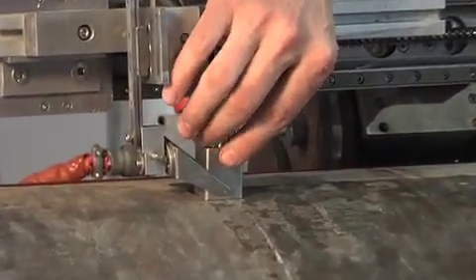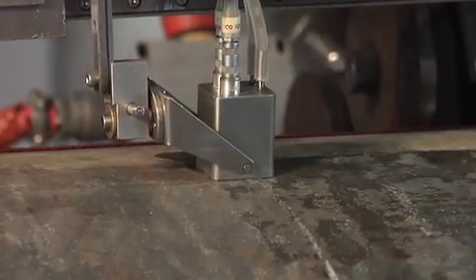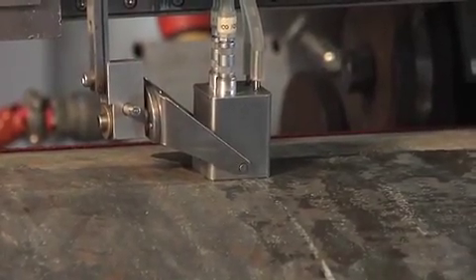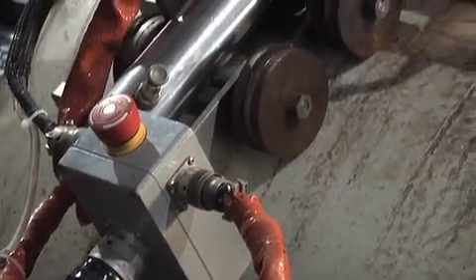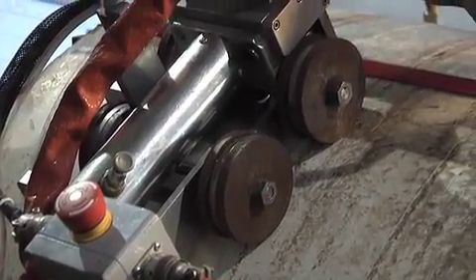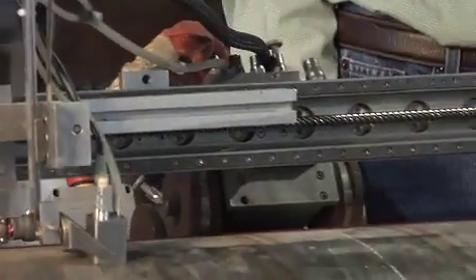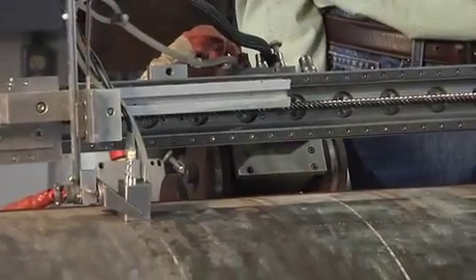The transducers are just normal transducers. We also have high temp transducers that could go up to 900 degrees. These scanners can go upside down all around a pipe without having to be held on. They're held by magnetic wheels, and as you can see, doesn't come off easy.